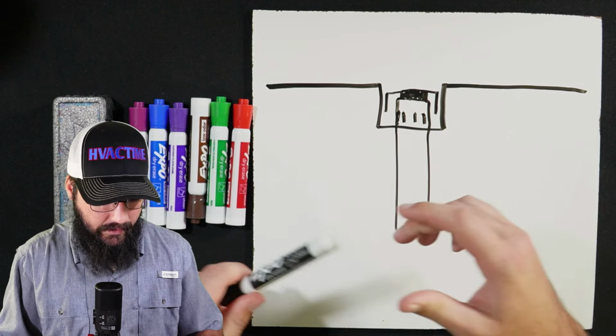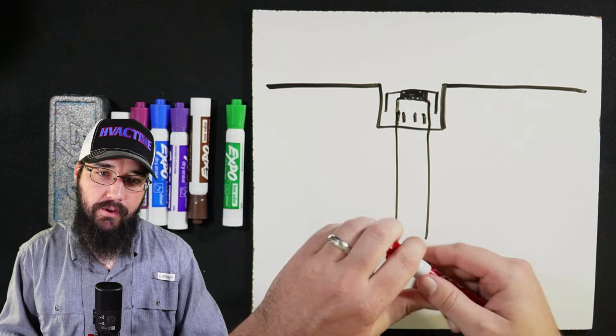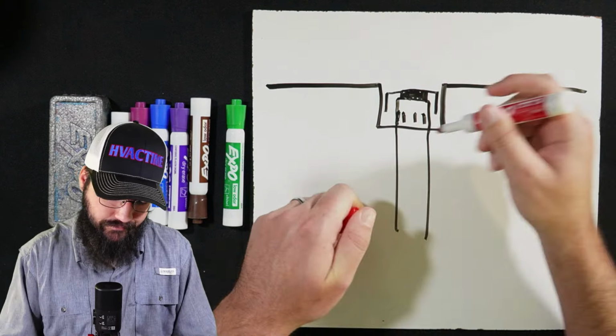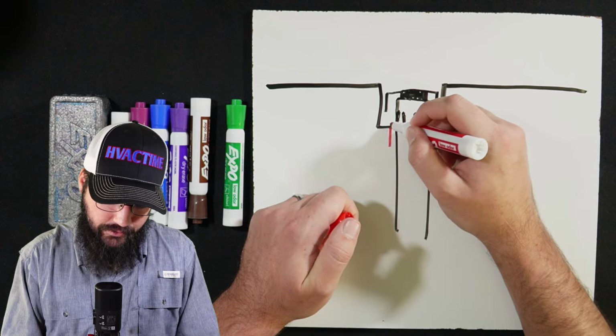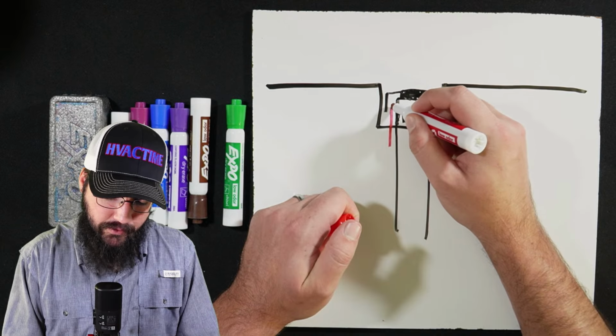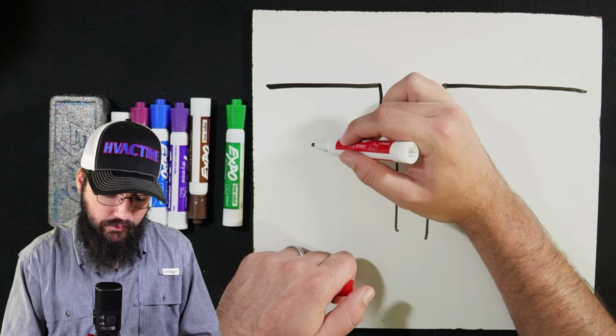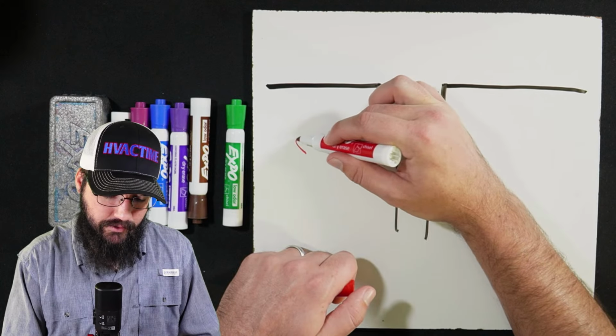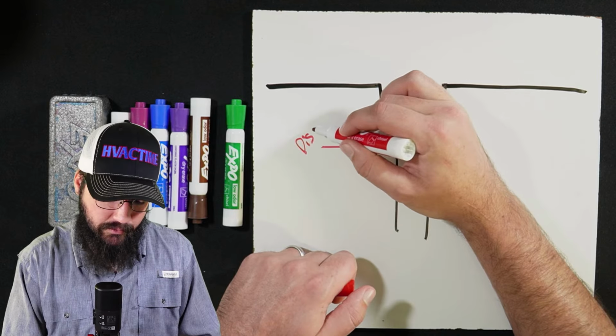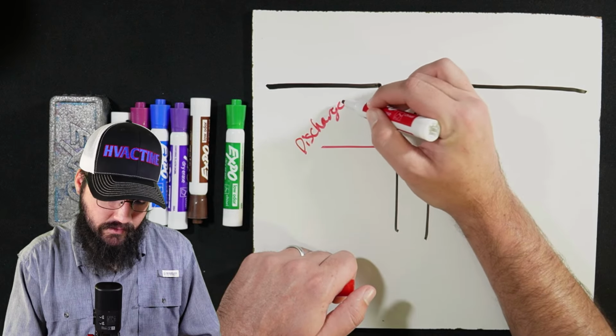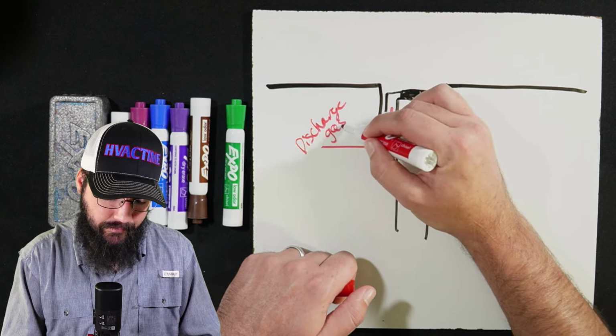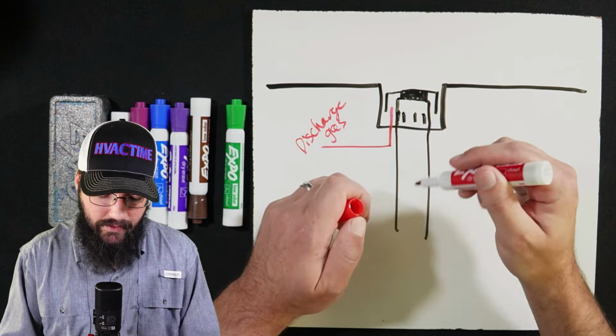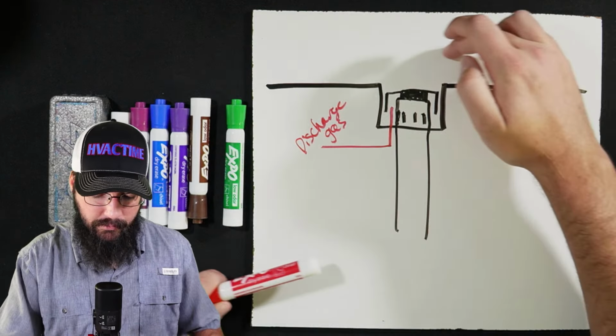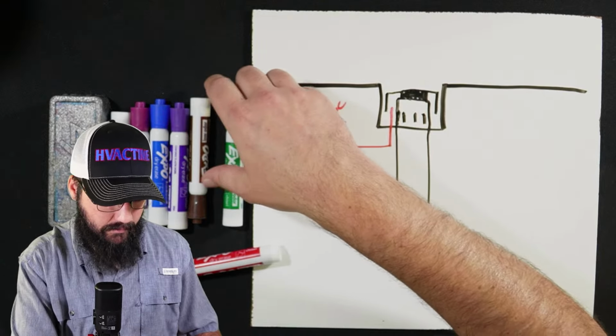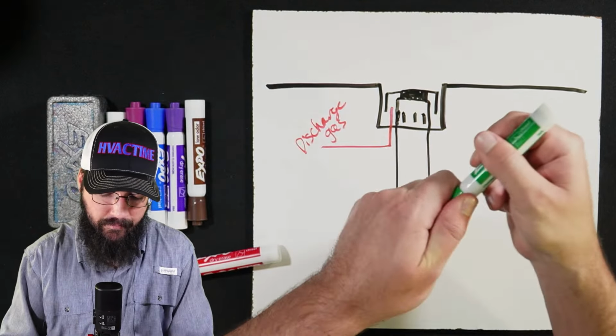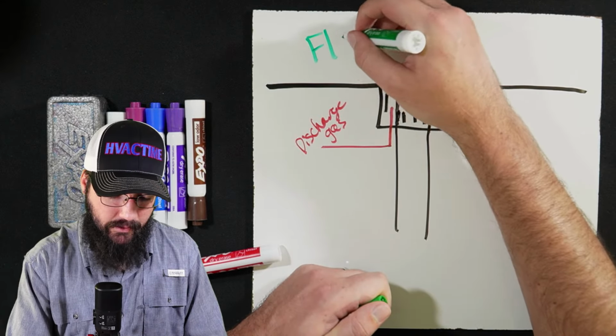Now there is a component called the bubbler tube. I'm going to draw this in red intentionally. So the bubbler tube comes up right here, and this comes back to the discharge, or top of the condenser, somewhere in there. Okay, this is discharge gas. So what's happening is this up here would be our flash chamber. Okay, so bear that in mind. We'll go green. So this is our flash chamber.